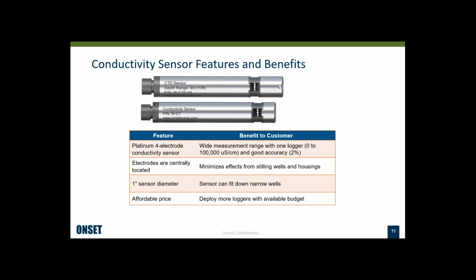The electrodes are centrally located within the sensor so that they're not right on the outside. And the advantage of that is that the electrodes are not affected by the well walls or anything else that the sensor may be up against. So that's important. The sensors are 1 inch in diameter, so they can fit down fairly small wells. Of course, that's limited by the logger if it's attached to the logger, or it can be on the cable, which is less than 1 inch in diameter. So you can get down the narrower wells using the MX802 with a cabled sensor. And we affordably price these. I'll talk about the pricing in a little bit.